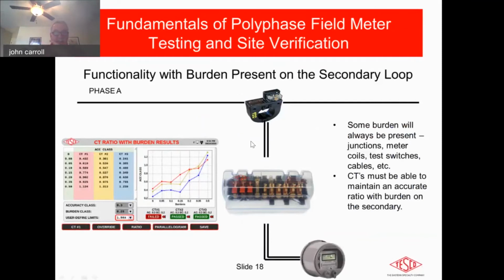Here is a typical example of a test that we did. On the left-hand side, there's a little screenshot of what we actually received as the test results. Now remember, burden's going to be present no matter what. We just described a setup where the cabling between the meter itself, the meter socket, and the CTs was very short. That's not always the case. There are sometimes cabinets which could be 20, 30, 40, 50 feet away. They don't want that. They want to design them as close as possible, but sometimes circumstances prevent that. So now they have to take into account a whole set of wiring, both to and from the CT. That's a lot of wiring, and wiring is resistive, and therefore it has a burden.